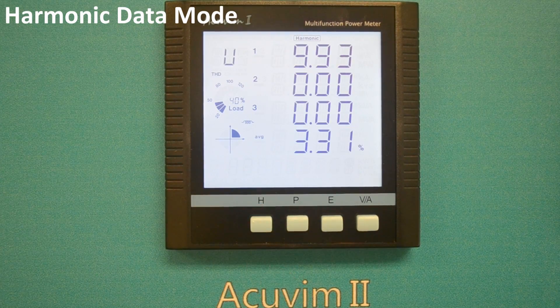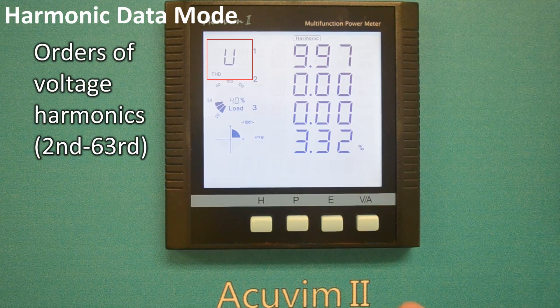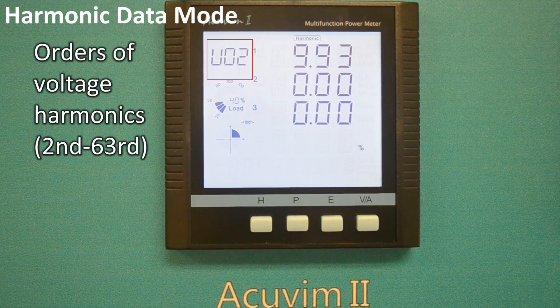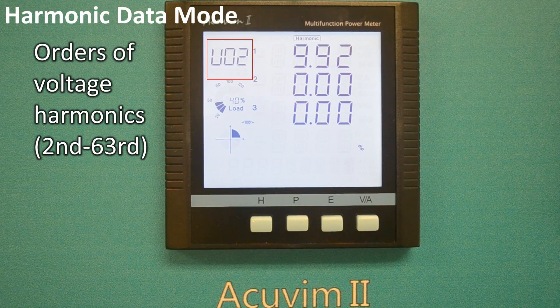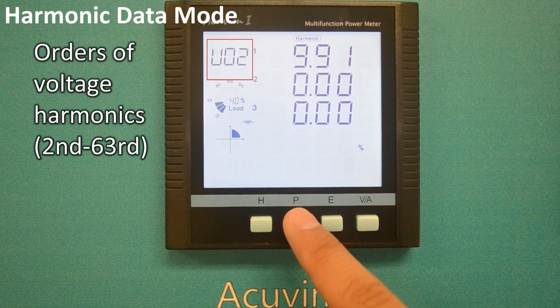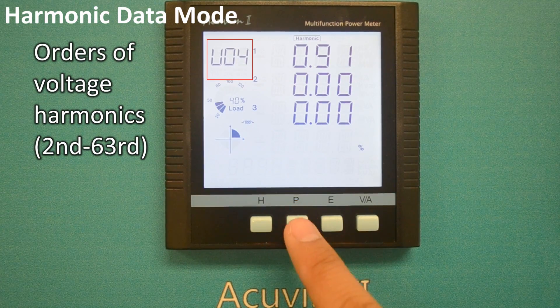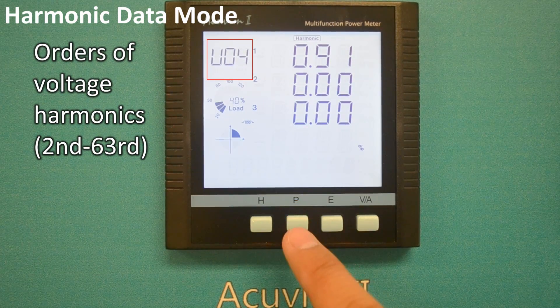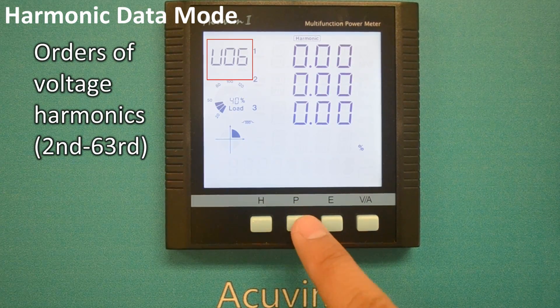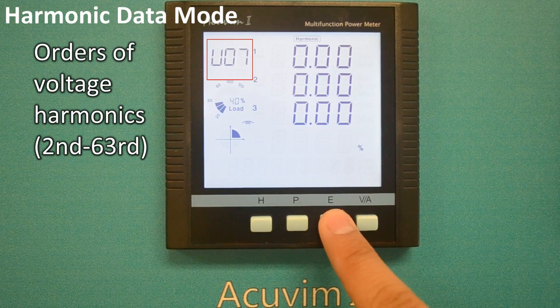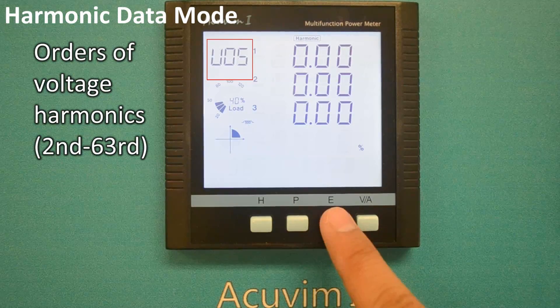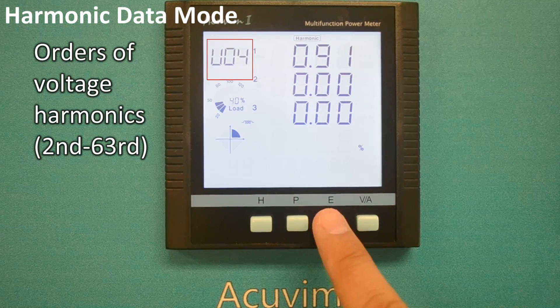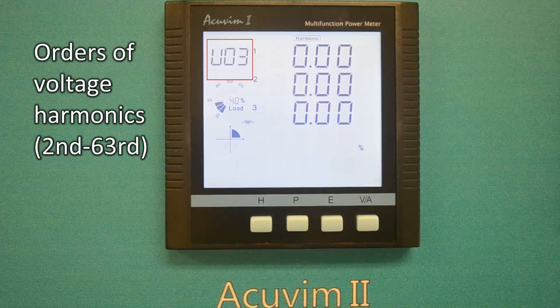Press the VA key on the voltage THD screen to display each order harmonic data of voltage. Pressing P will show you each order of the harmonic data for voltage, and pressing E will show you the order in reverse sequence. The data on the base AccuVim2 is from the 2nd order to the 31st.